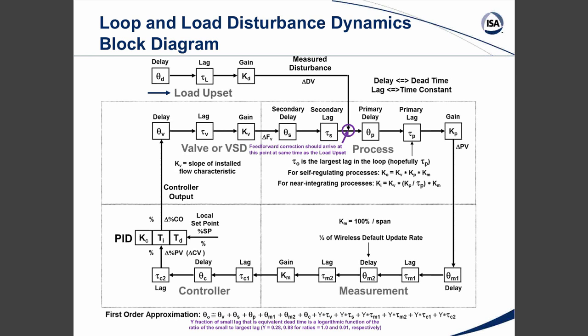When you make a bump test, et cetera, in the process, or by trending during your process dynamics, you would know by how much you change your output and what the change was there. But in the disturbance, there's not necessarily available information to calculate this gain, even the delay. Yeah, it gets to be a little complicated because it also depends upon your feed forward scale.